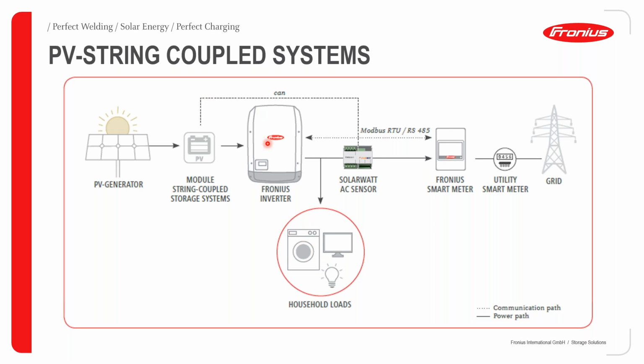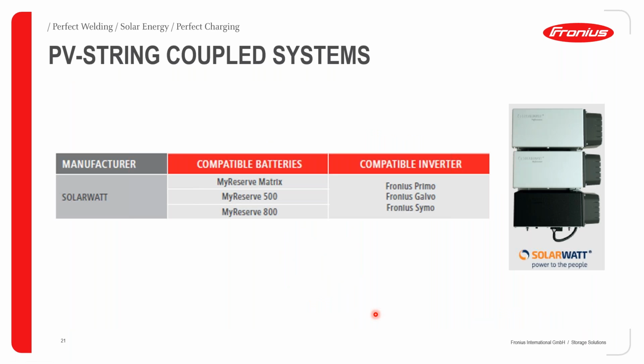So the main advantage of a PV string coupled system is that you can actually achieve module based storage. In the case that your irradiation levels change throughout the day, you are more protected against that change. With the PV string coupled system, our Fronius inverters, most notably the Fronius Primo, the Fronius Galvo, and the Fronius Symo, are tested to work with the SolarWatt. The SolarWatt is the PV string coupled DC storage system, and these are the different variants from the SolarWatt company that they do produce.